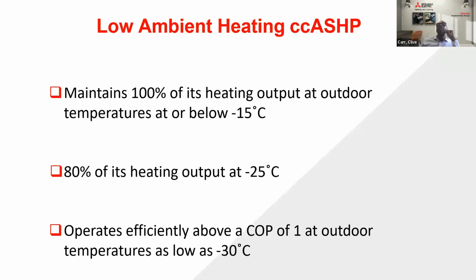So, taking a look at the product features. Again, what defines a cold climate heat pump? There are three factors that define a cold climate heat pump: the amount of heating that you get at low temperatures, the efficiency of the heat pump at low temperatures, and the operating range of the heat pump. So you've got to be able to operate to a very low temperature range. We are at approximately minus 30 to minus 35. We are not at minus 40 for heating as yet, but we continue. The industry continues to get better.